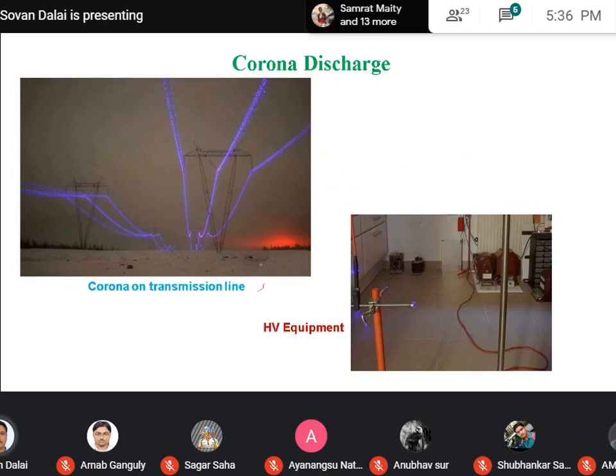Obviously, this picture is not actually of a transmission line. This is an animated picture. This is the transmission line. If corona occurs, it will look like this. And this is another picture of corona, where high voltage equipment is subjected to, or supplying, very high voltage for some specific purpose. In order to avoid that corona, generally we use bundle conductors to improve the corona performance of the transmission line.